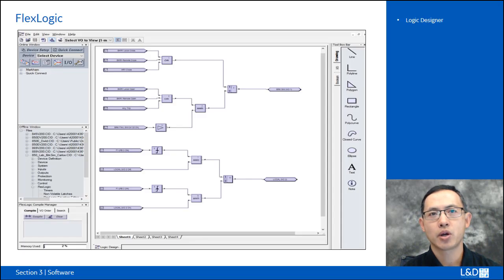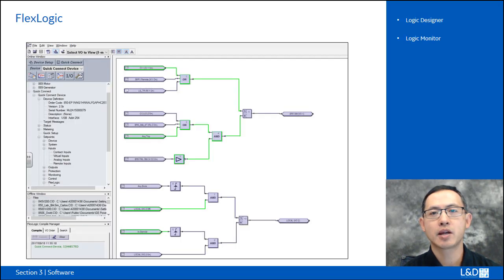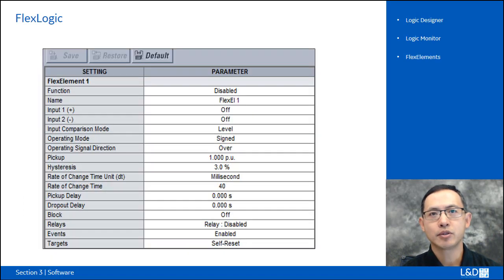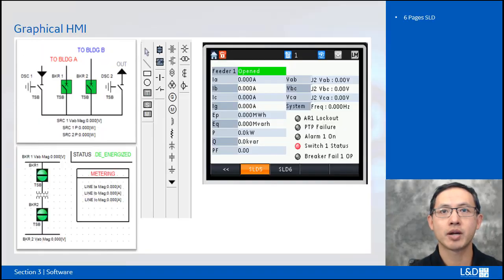Flex logic can be used to design programmable logic schemes, as well as monitoring the state of each input and output. Flex elements can be used to create flexible, customized protection elements. User configurable single-line diagram up to 6 pages for comprehensive switchgear control of up to 3 breakers and 9 disconnect switches, with color display for local control, system status, and metering. The provision of such one-box powerful control and display capability within the relay eliminates the need for external controls, switches, and annunciations on the panel, reducing the equipment and engineering costs.